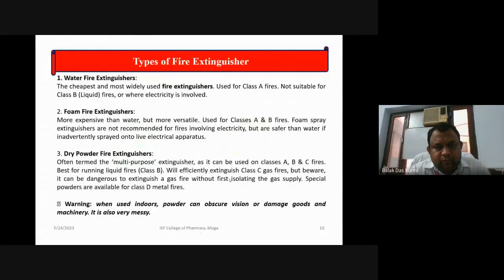So, after understanding the fire source and fire theory, we will discuss the fire extinguisher: on which type of fire, which type of extinguisher is to be used. Number one, water fire extinguisher. When water is used, we can say it is the cheapest and most widely used fire extinguisher. It is used for class A fire and is not suitable for class B fire or where electricity is involved. So we will keep in mind that the water fire extinguisher is only used for class A fire.